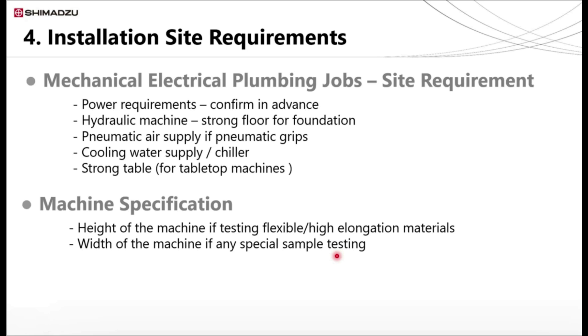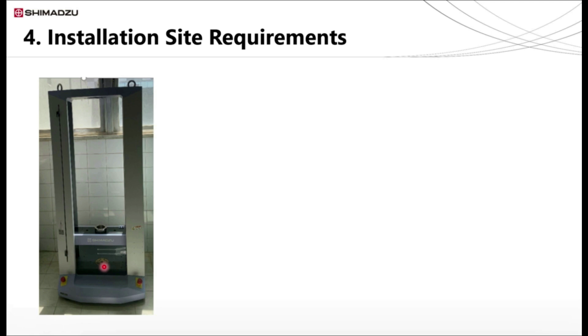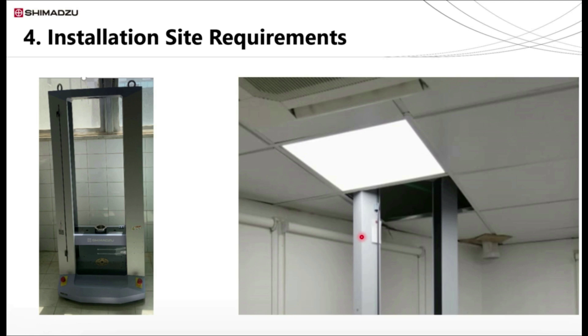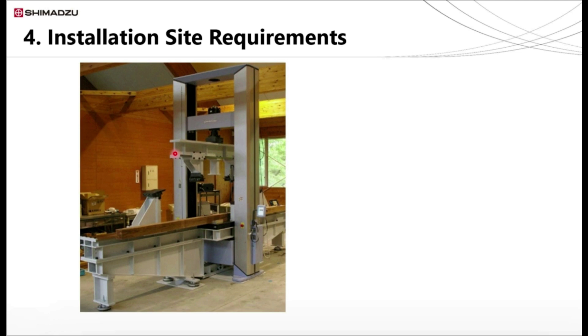Some case studies: I have one experience where we installed a tabletop machine on the floor as the customer-supplied table was not adequate to withstand the machine weight. You can see here, at another customer's place we installed the machine by removing the roof as the height was inadequate. Also, as I mentioned, some non-uniform or full-scale specimens may require a custom-made UTM. So if your sample is unique, discuss these details in advance with the supplier in order not to lose any money.